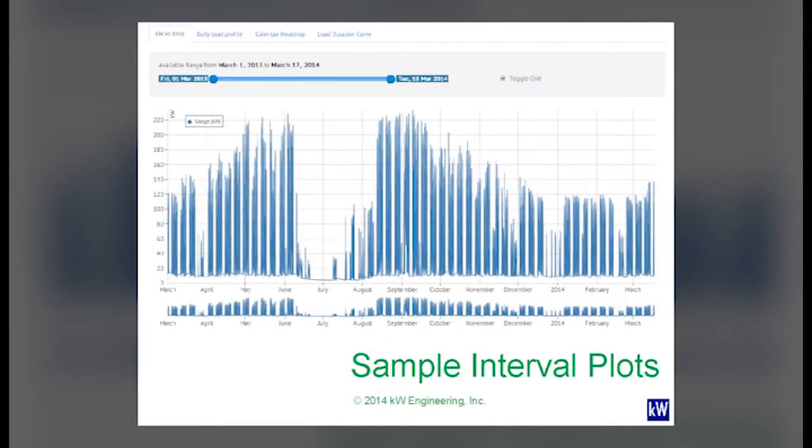This is a whole year of interval data plotted for a school. And then you can zoom in on some of these areas and see what's going on. You can see very clearly what the timeline of my summer break was here, and my holiday break around the end of the year. Here, you can even see spring break right here.